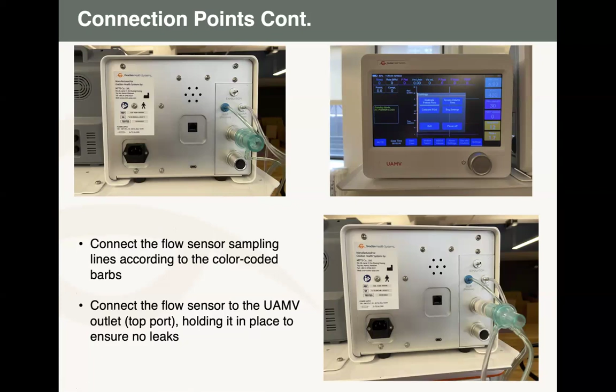So once you have done your connection, whenever you are doing it, because with the current event, you can even keep the flow sensor at the breathing circuit, but the machine will tell you to open the flow and you can continue. Once you are ready for flow sensor calibration, you just tap the setting, as shown in the lower picture, and this screen will pop up with calibrate patient flow, calibrate FiO2, leak testing, and all of those things. Our interest here for now is just patient flow. Once you touch on that, the machine will tell you to open the flow sensor, which means if it's connected to something which is blocking, it should be taken out.